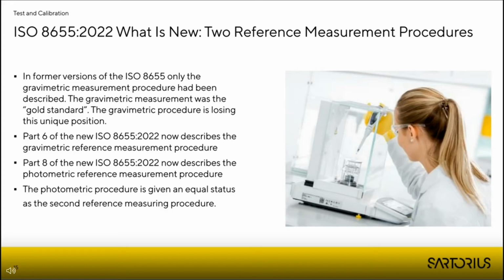One of the main new points in the new ISO is that there are now 2 instead of 1 different reference measurement procedures included. In the former ISO, only the gravimetric measurement procedure had been described. This gravimetric measurement procedure is now losing its unique position. Part 6 of the new ISO describes the gravimetric reference measurement procedure, and part 8 describes the new photometric reference measurement procedure. The photometric procedure is given an equal status as a second reference procedure.